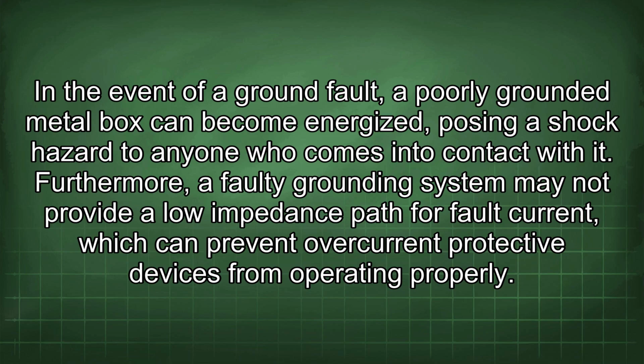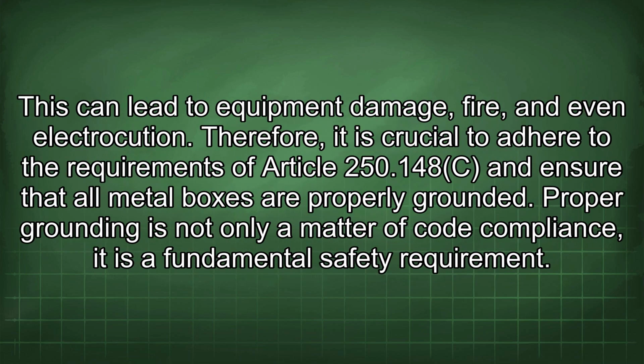Furthermore, a faulty grounding system may not provide a low impedance path for fault current, which can prevent overcurrent protective devices from operating properly. This can lead to equipment damage, fire, and even electrocution. Therefore, it is crucial to adhere to the requirements of Article 250.148c and ensure that all metal boxes are properly grounded.